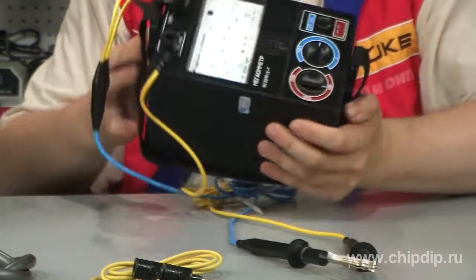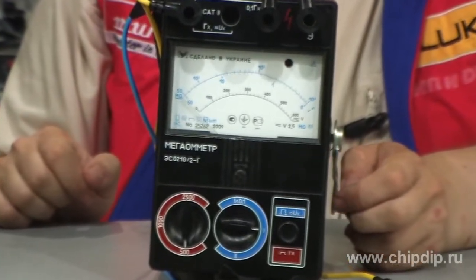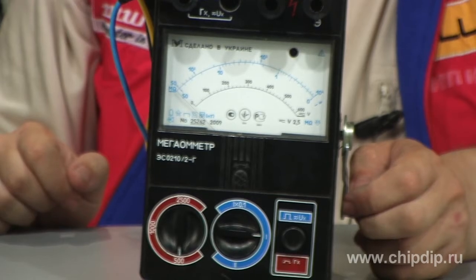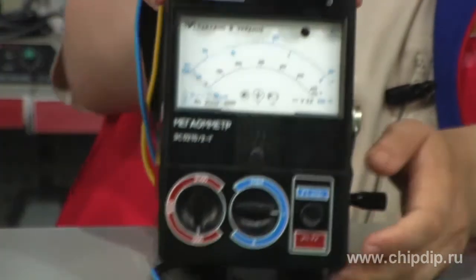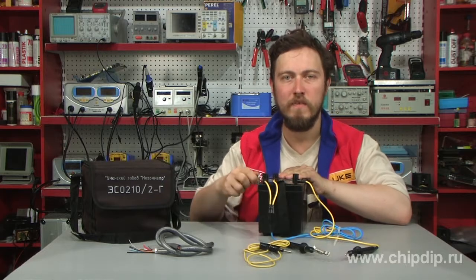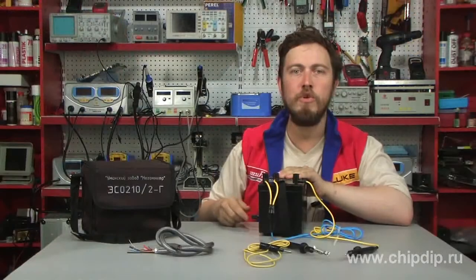The ES0210/2-G is designed for measuring insulation resistance of dead electric circuits, as well as for measuring AC and DC voltage. The megohmmeter is powered by a built-in electromechanical generator. The rotation velocity of the handle must be from 120 to 140 rotations per minute.